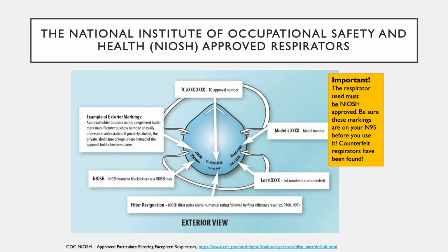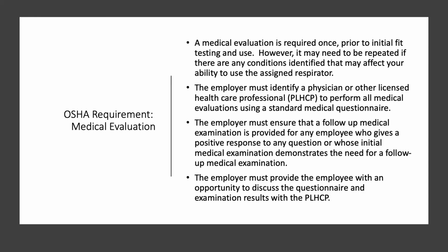Now, while this is the responsibility of your employer, you should also check it before you wear it. So you can look at the brand name, look for the NIOSH logo, the filter class, the efficiency. You can even look at the lot number, the model number, etc. You can look to see if it's in good working condition, make sure there are no holes, no torn or frayed straps, etc.